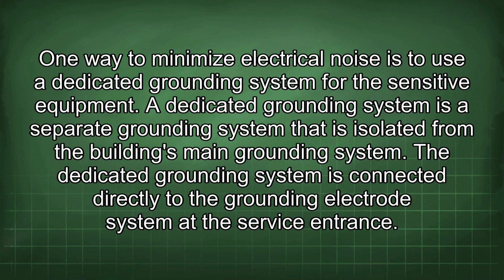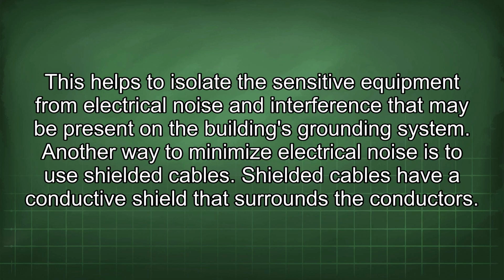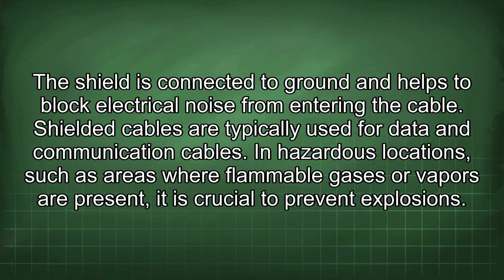The dedicated grounding system is connected directly to the grounding electrode system at the service entrance. This helps to isolate the sensitive equipment from electrical noise and interference that may be present in the building's grounding system. Another way to minimize electrical noise is to use shielded cables. Shielded cables have a conductive shield that surrounds the conductors. The shield is connected to ground and helps to block electrical noise from entering the cable. Shielded cables are typically used for data and communication cables.